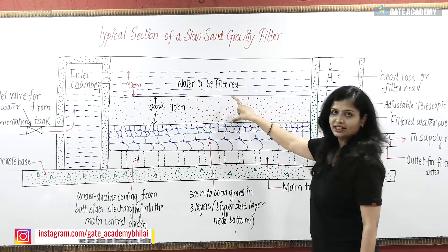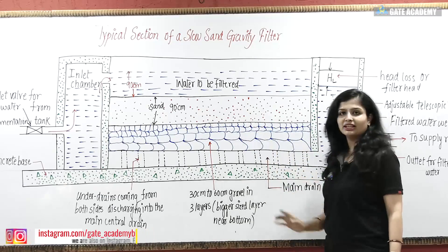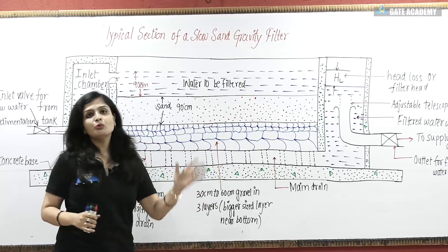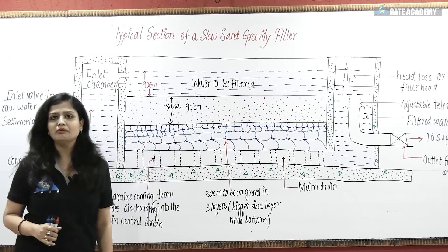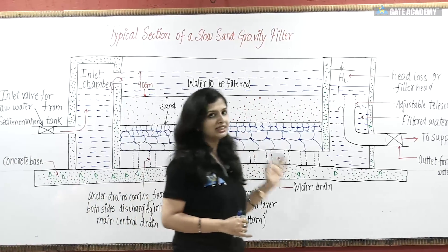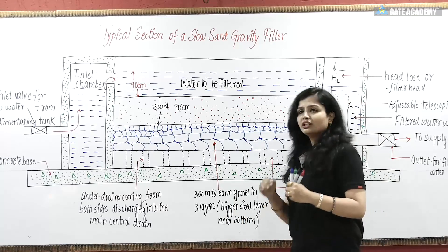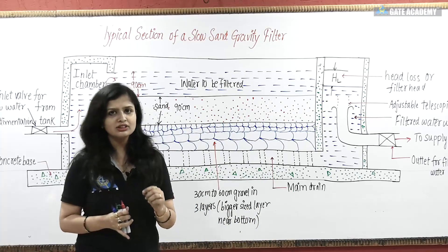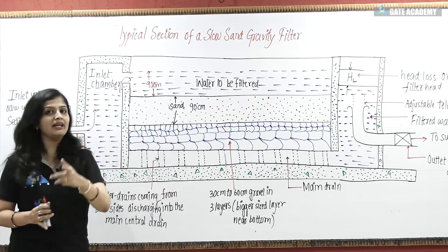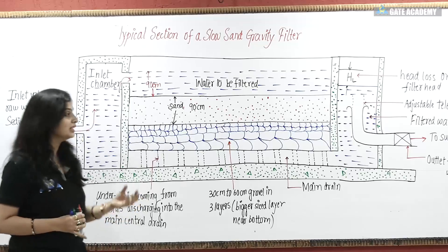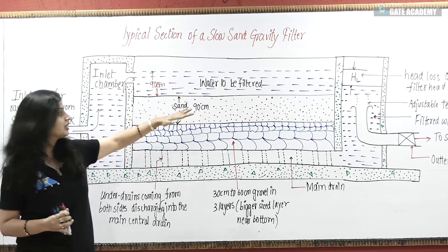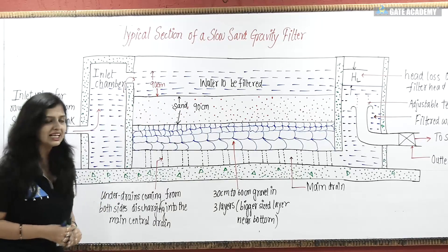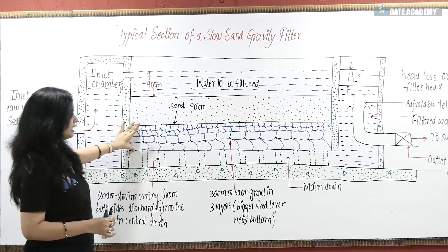Now let's talk about the filter media material. This sand layer has a depth of 90 to 120 cm. We will place the sand in two or three layers, but the sizes vary. The finer size sand particles are placed in the topmost layer, which relates to mechanical straining — smaller voids remove impurities. So the finer sand particles are in the topmost layer, then medium size, then coarser particles of sand.